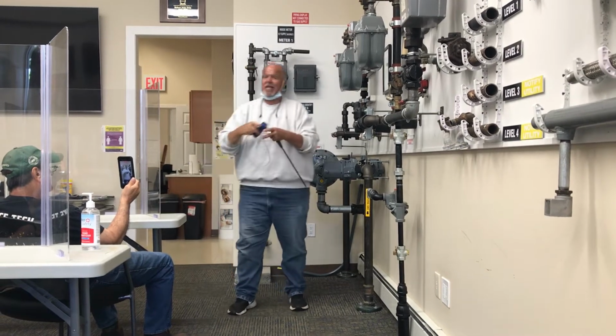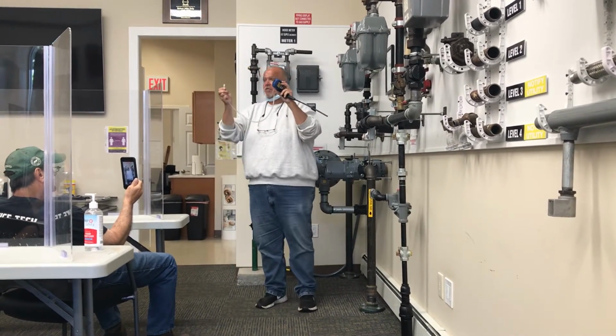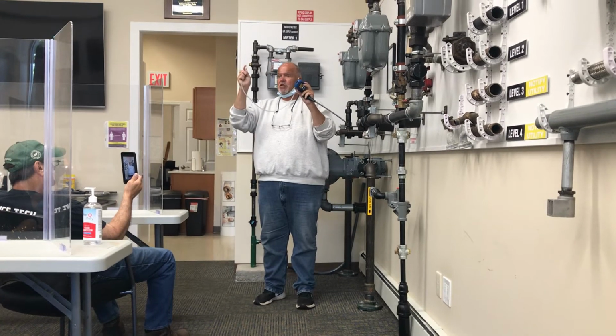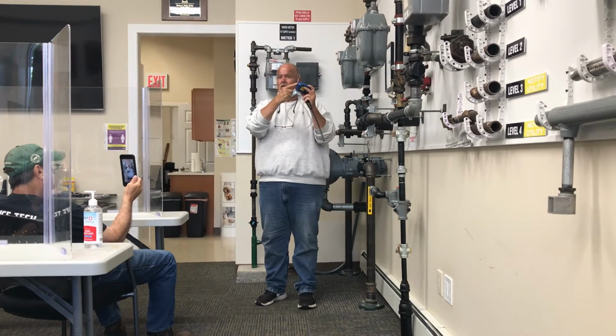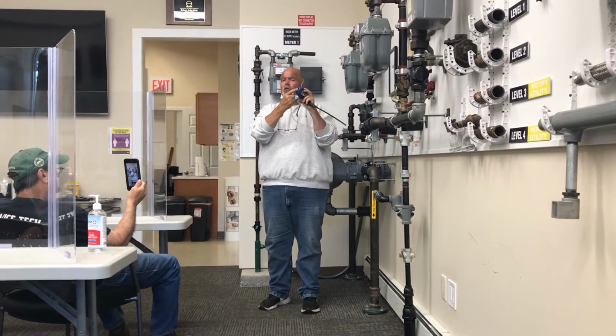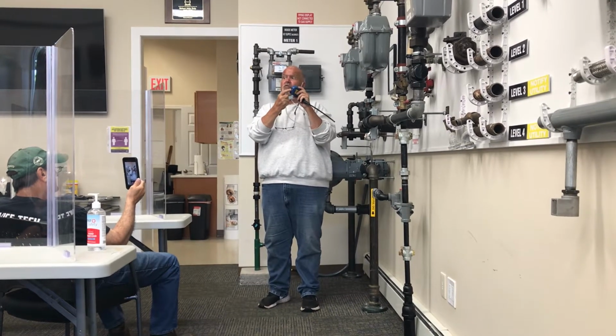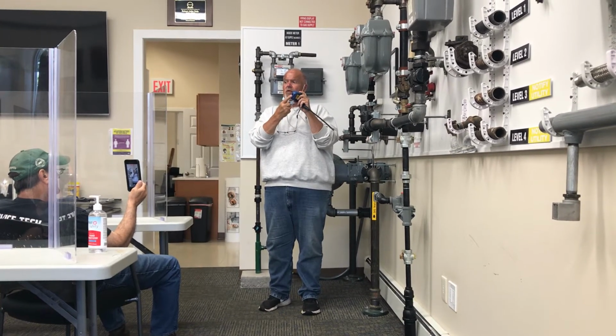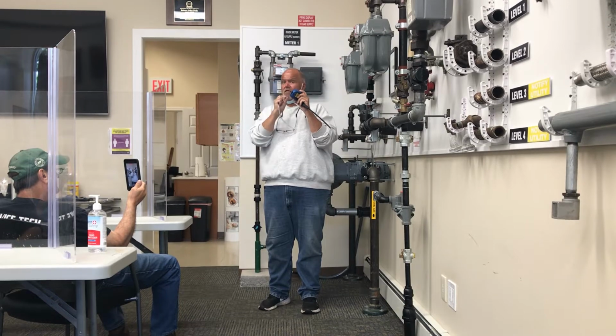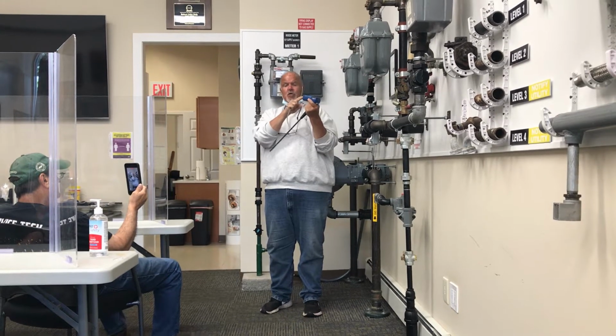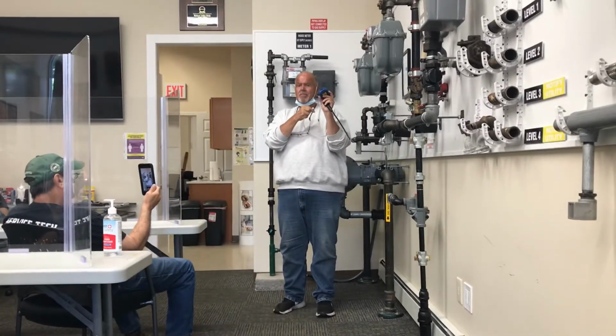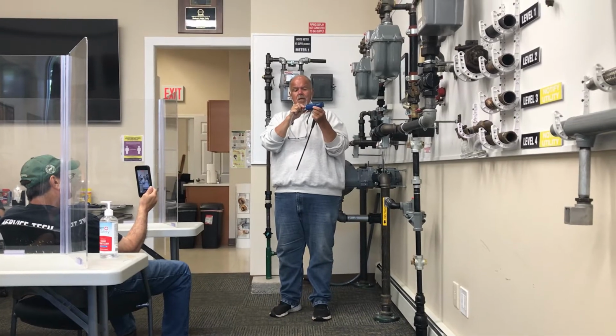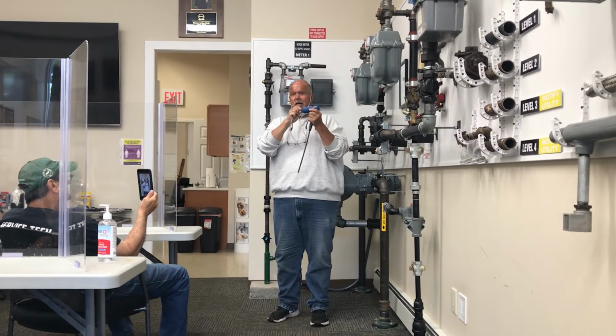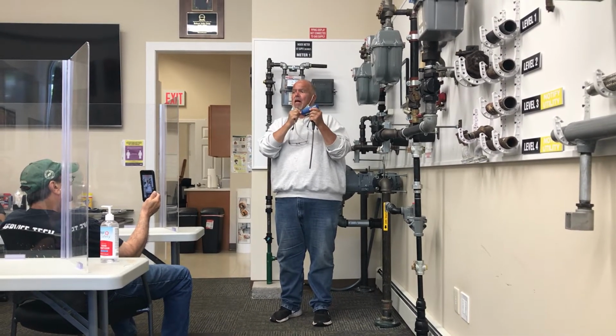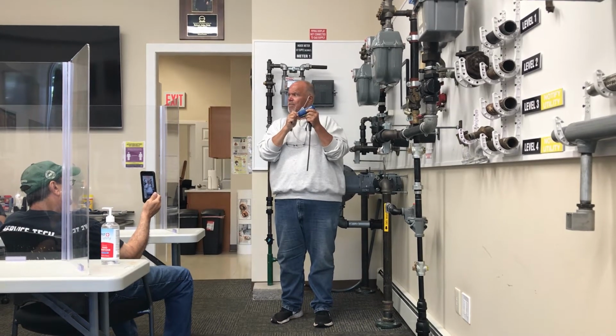Now you're going to connect it to the combustible gas detector. Line up the keyway connection on the connector to the device. Also, just note that there's a filter inside here at this connection point. There's a small cotton filter. You should be able to see it and it should be white. Line up the keyway, push it in, and it's about 1/8 of a turn clockwise and it will lock.